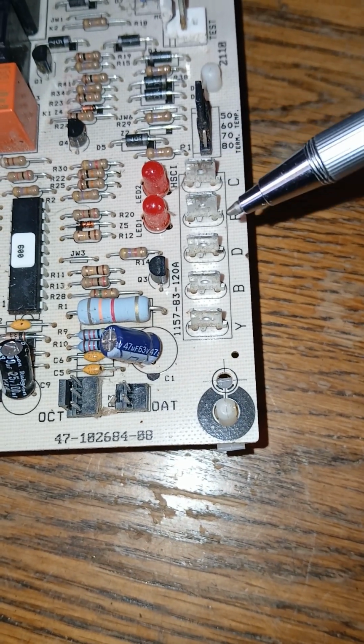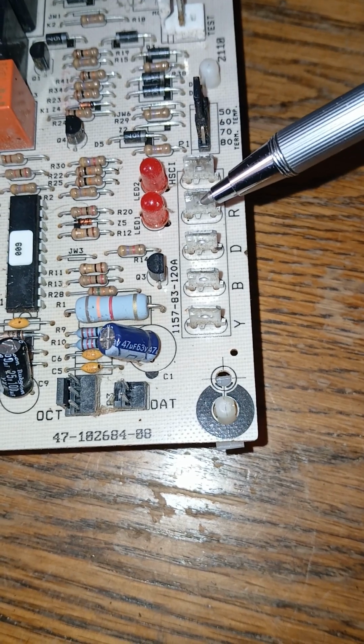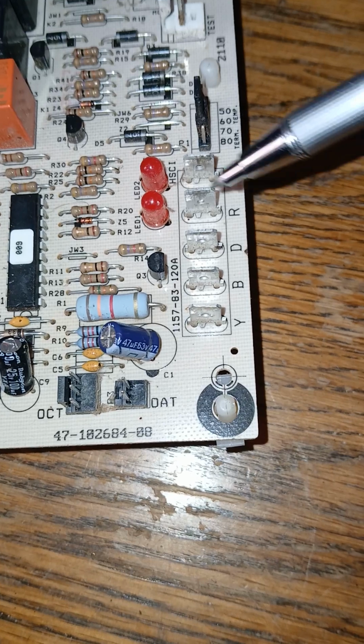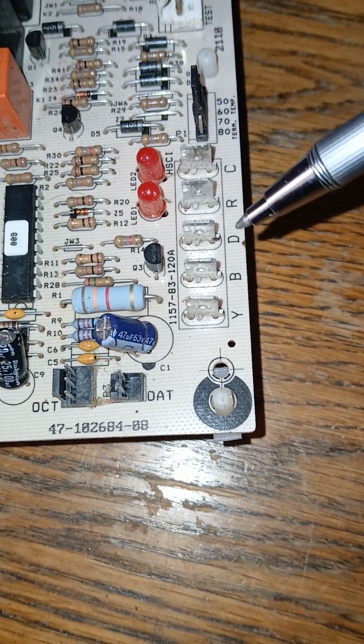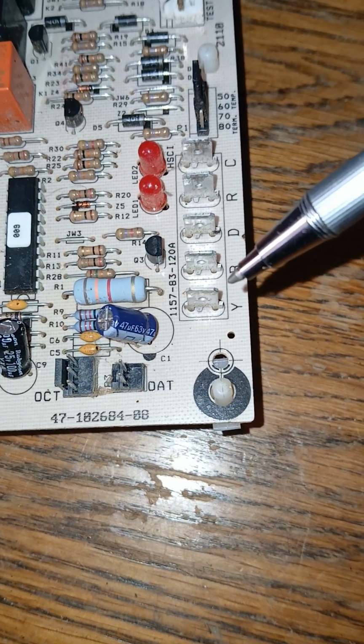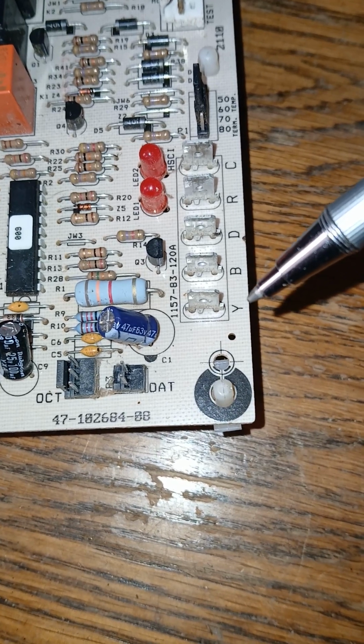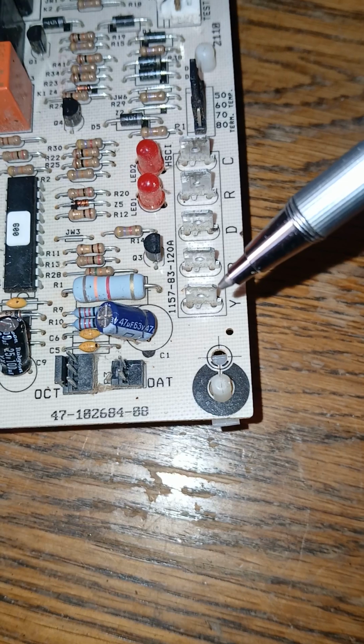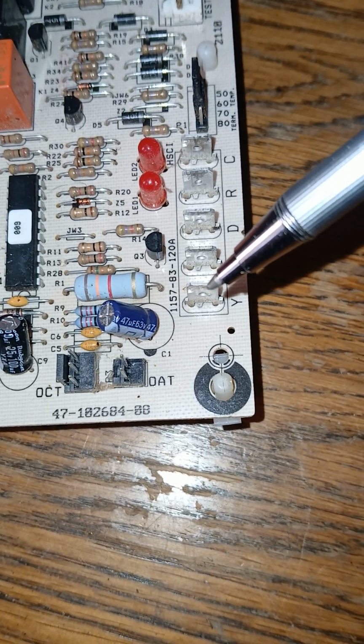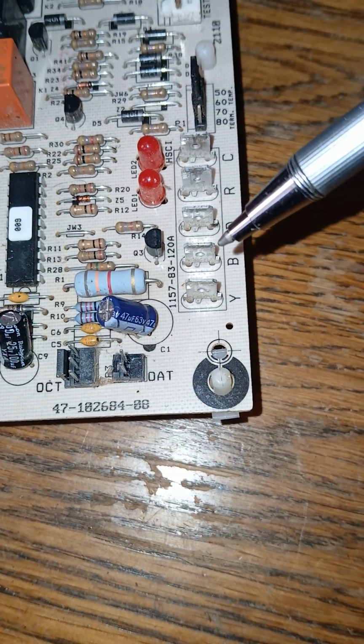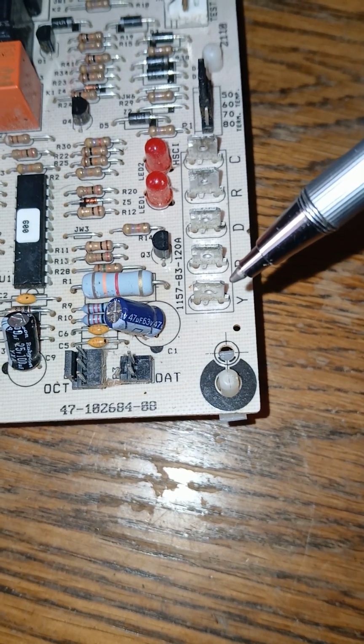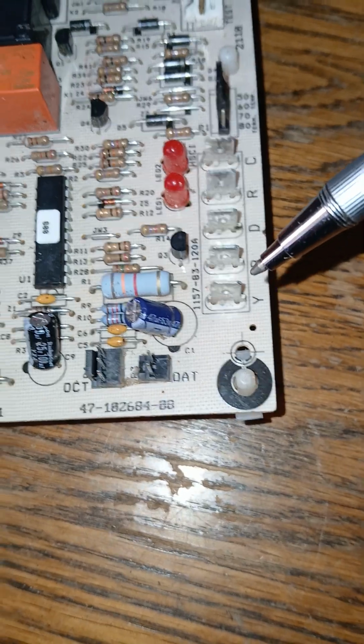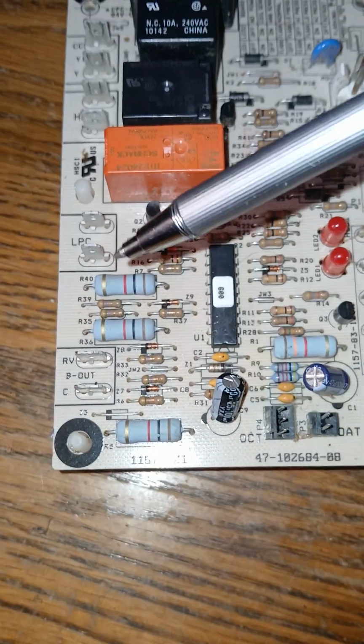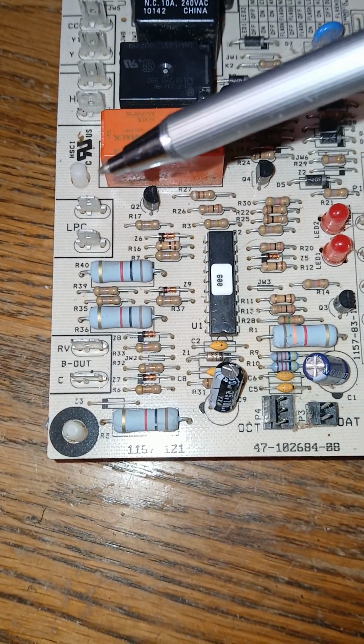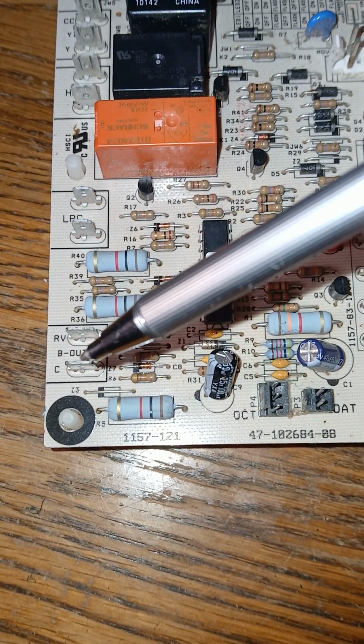So again, to recap, we have a red wire. We have the red 24 volts, the C outgoing. That should return the voltage back, the low voltage. And when it calls for Y, which I'm thinking would be cooling in a heat pump, perhaps a gas furnace may be different, but in a heat pump it may be cooling, or it could energize heat once the reversing valve is energized. So it depends on the situation. Anyway, we have Y, and then Y would jump over here. It would run through a sequence of operations, the low pressure and the high pressure switch or whatnot. And then at this point we have the terminals that would go out to the reversing valve, but we'll cover that in a bit.